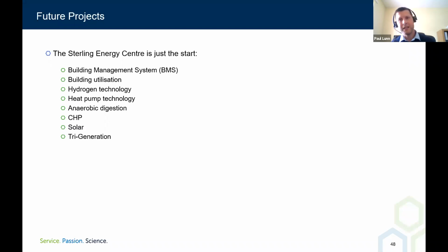CHP isn't the only thing Stirling is looking at. One feature that comes with the CHP facility Clarke Energy are installing is a building management system and energy management system as part of the project. This building management system is being cascaded throughout the site, a Siemens Desigo building management system with a power management tool. It can help us monitor the efficiencies of the system, tracking the gas and water going into the boilers, the steam being generated, and the gas and subsequent power from the alternator set, as well as help smooth out our peak demands.